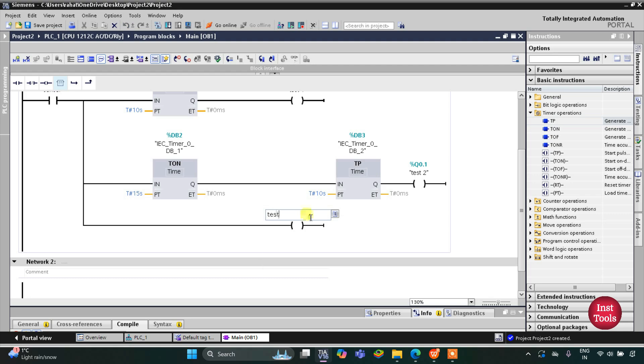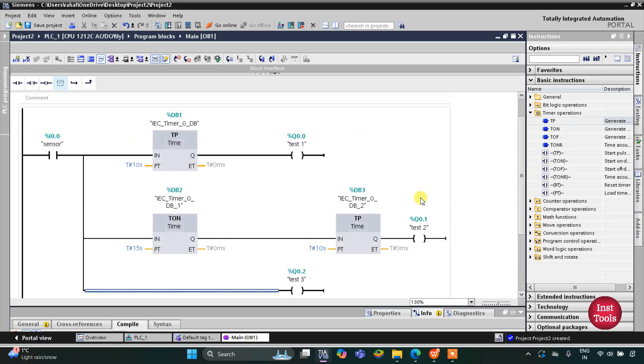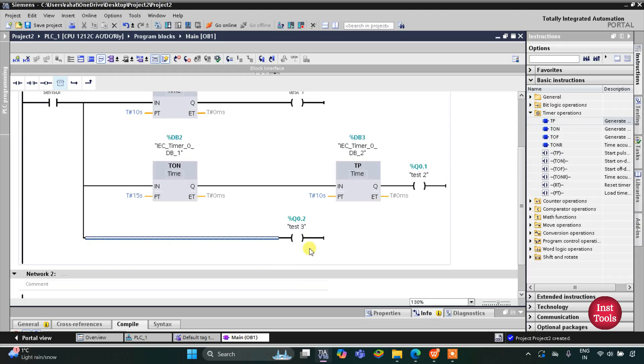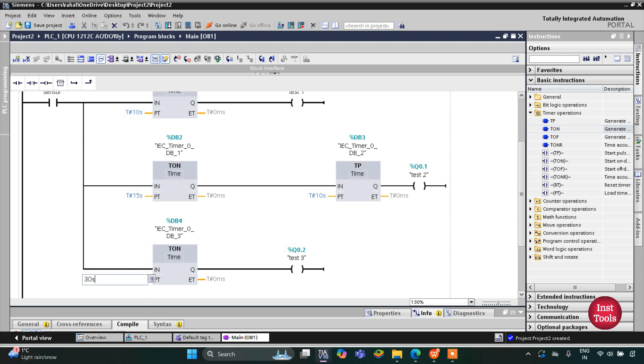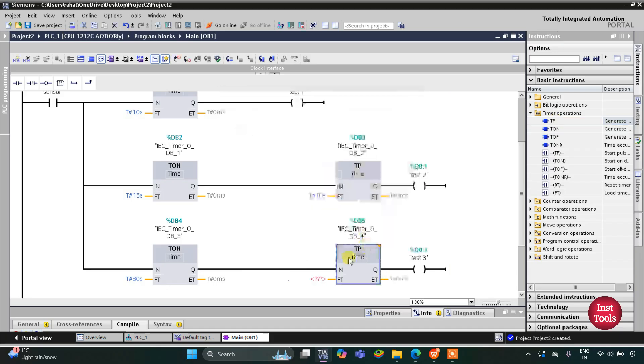This coil will represent Test 3, which runs after Test 2. The calculation is: Test 1 runs for 10 seconds, then a 5-second delay, then Test 2 for 10 seconds, then another 5-second delay — so 15 + 10 + 5 = 30 seconds total before Test 3 starts. We'll use a TON with a delay of 30 seconds, and then a TP that sends a pulse for 10 seconds only.